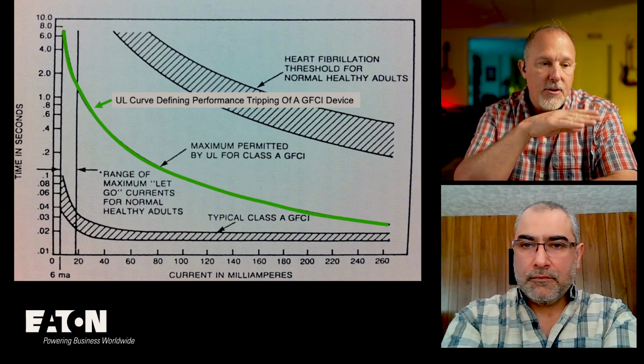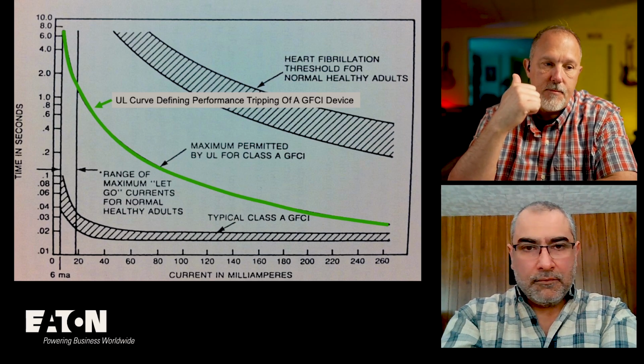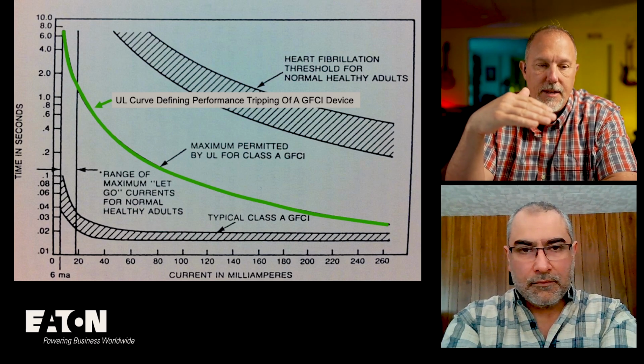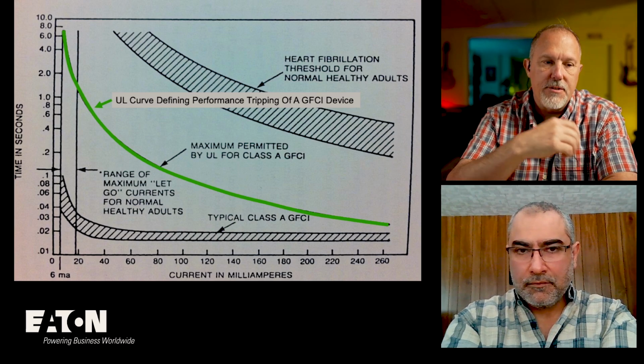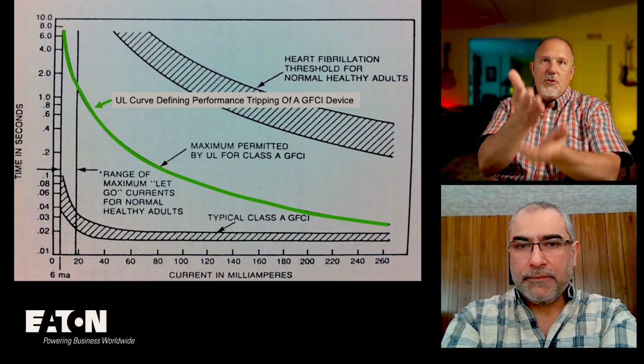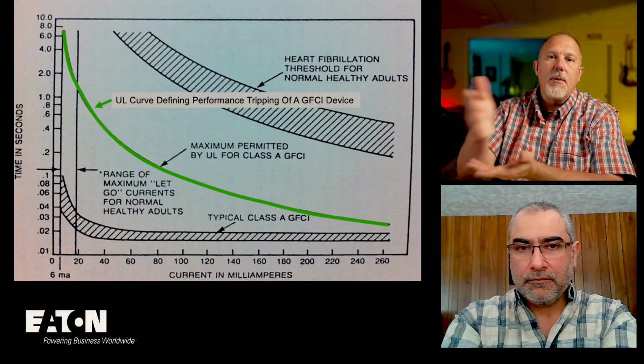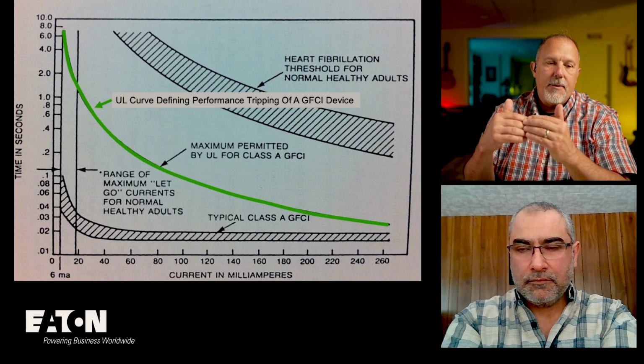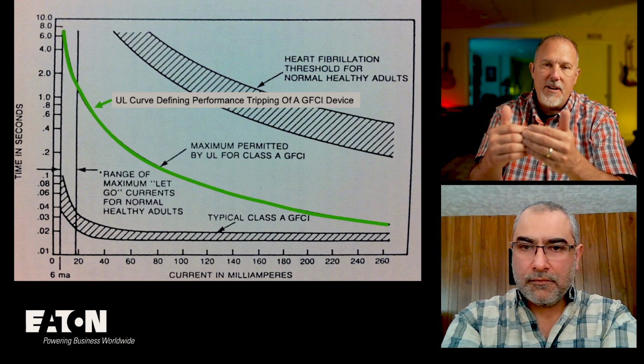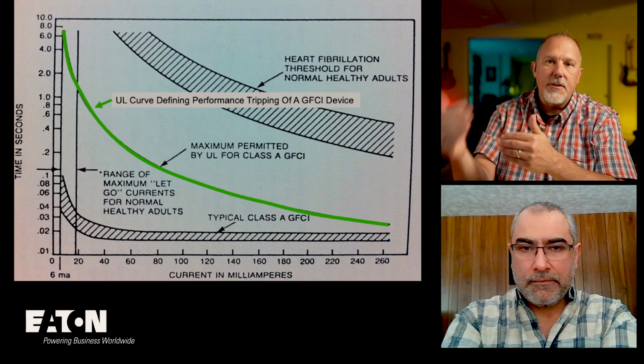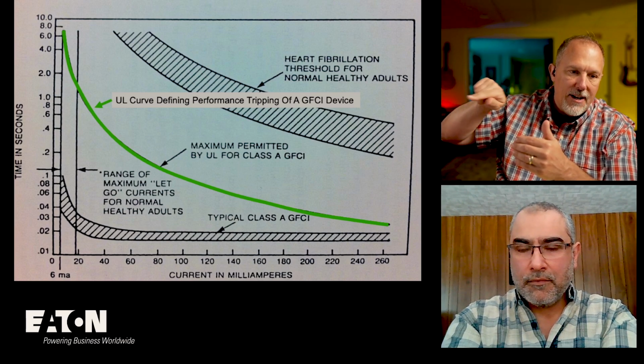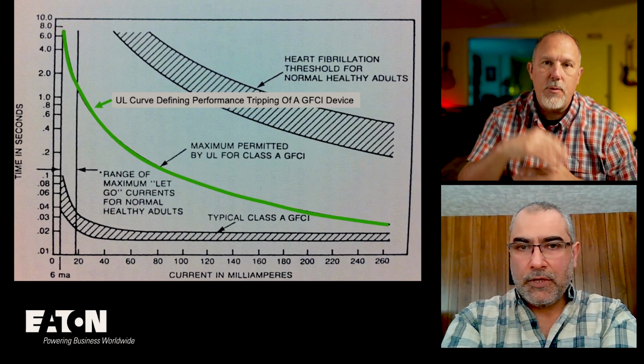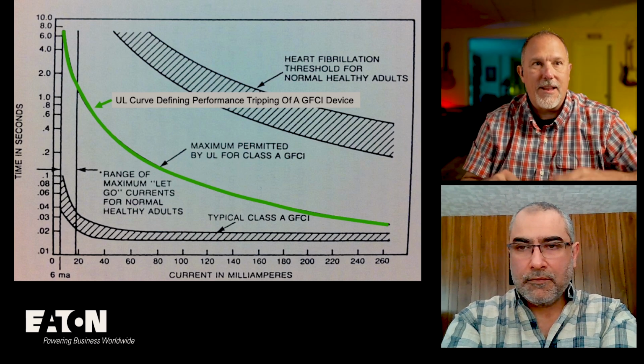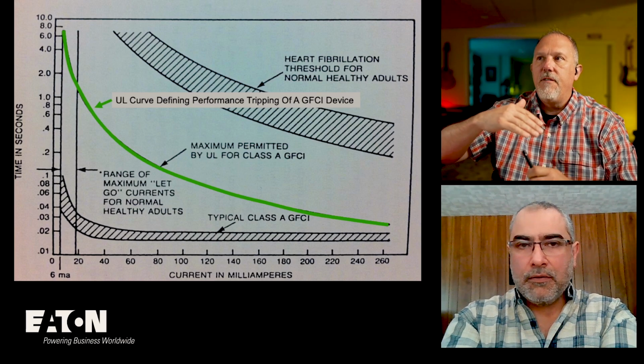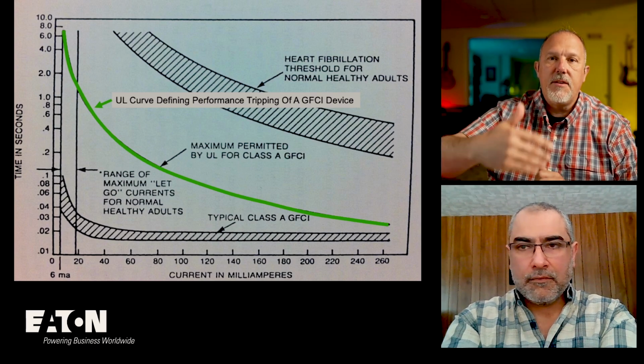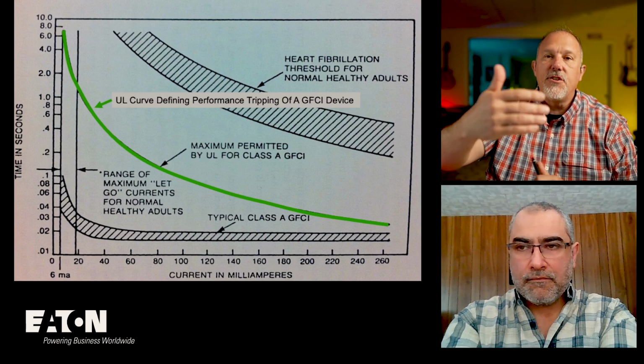So that green curve on this slide is the UL limit. And the curve that's lower is your typical Class A GFCI. So to your point earlier on the previous slide, a European type of RCD, that threshold's going to be higher because you're not worried about the green line in those other standards. You're worried about the line up here higher up, which is the fibrillation line. So you have more breathing room, so to speak, for the lack of a better term, right? You have more room for the amount of current that you permit to flow and for a duration of time.